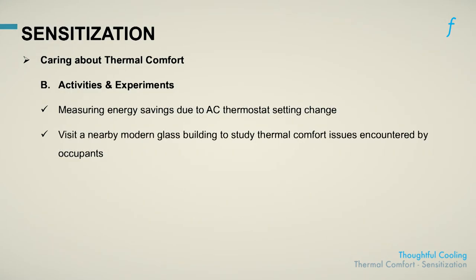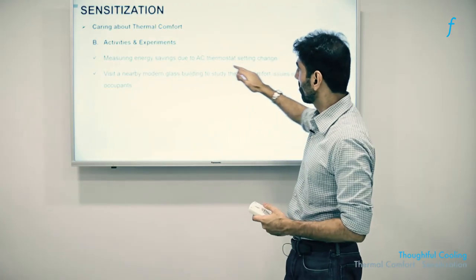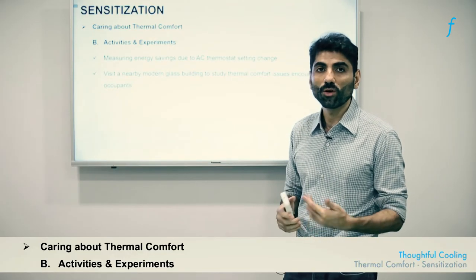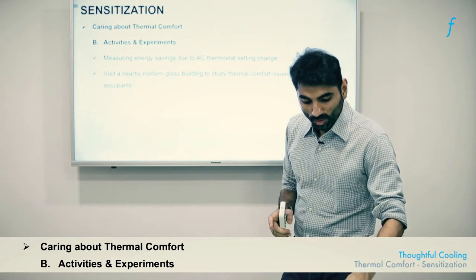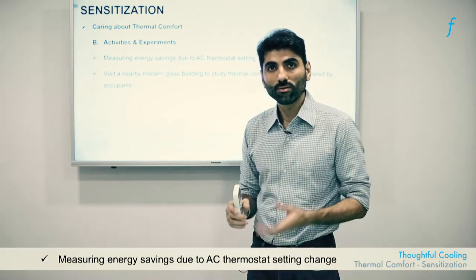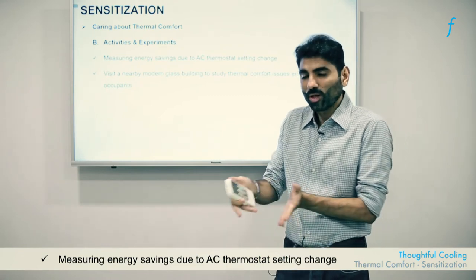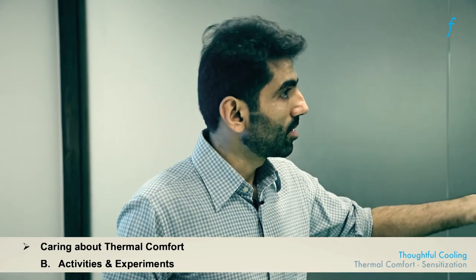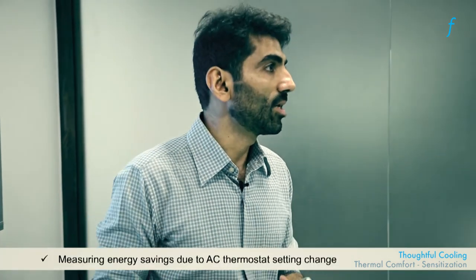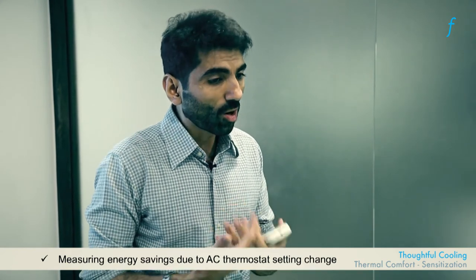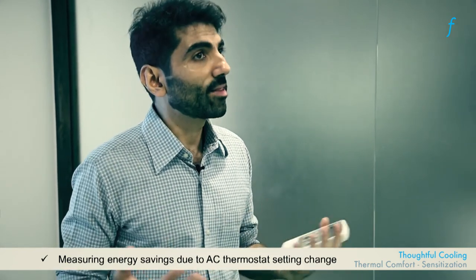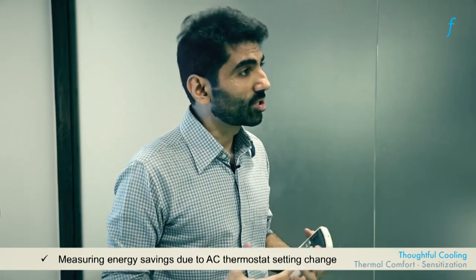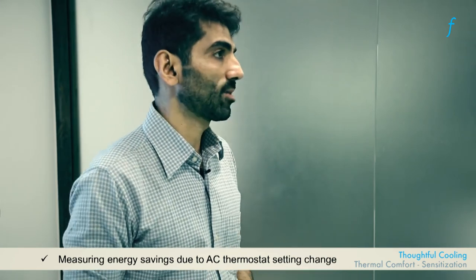Other activities could include looking at how changing the thermal comfort setting of an air conditioner affects energy and perceived comfort. If an AC is set at 22°C, one could measure energy consumption and note the thermal comfort felt, then change the set point to 24°C or 26°C and see whether thermal comfort really drops off as assumed. Is the energy conservation benefit adequate to justify a higher setting without meaningful compromise in thermal comfort?